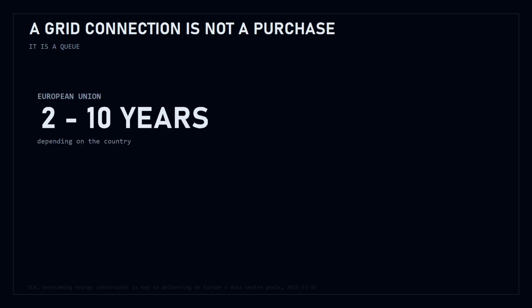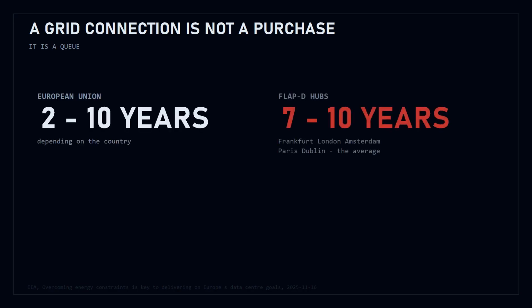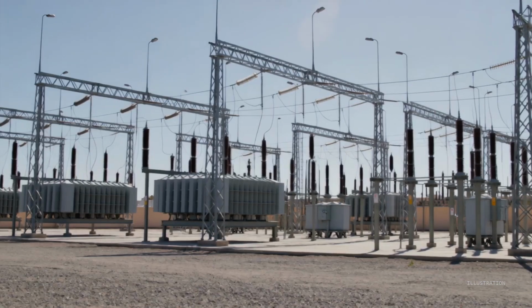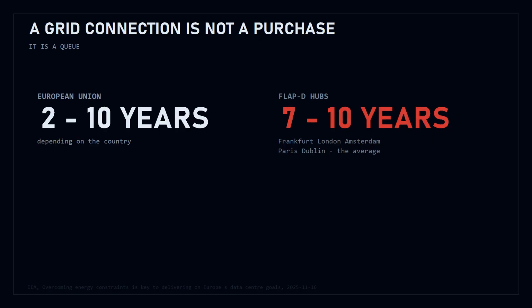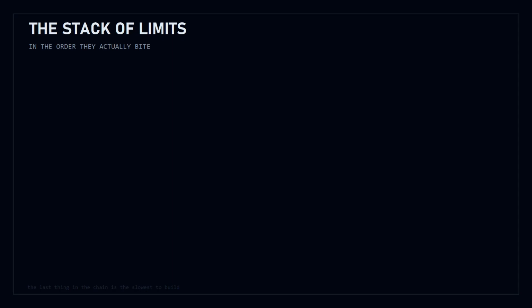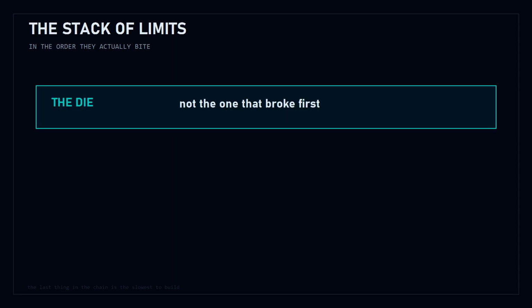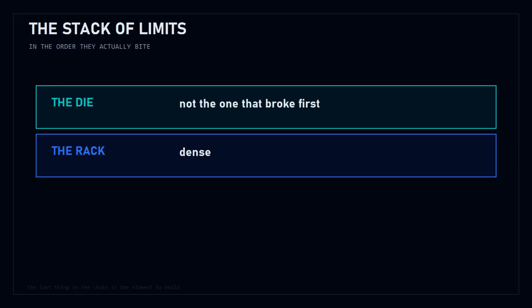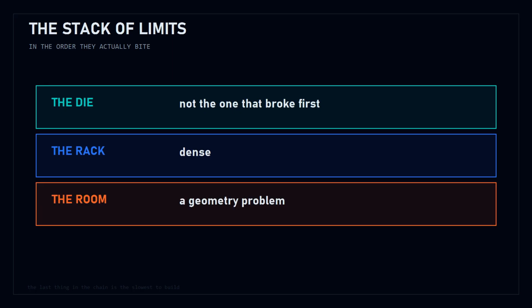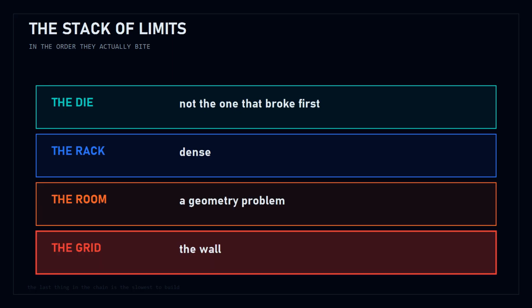A campus drawing hundreds of megawatts needs a grid connection, and a grid connection is not a purchase, it is a queue. In Europe's 5 biggest data center hubs, the IEA puts the average wait at 7 to 10 years. That was November last year. So the stack of limits, in the order they actually bite. The die is not the one that broke first. It has its own troubles, and they are the next episode. The rack got dense. The room became a geometry problem, and the grid is the wall. The chip did not get hotter. Everything around it got denser, and the last thing in the chain is the slowest to build.